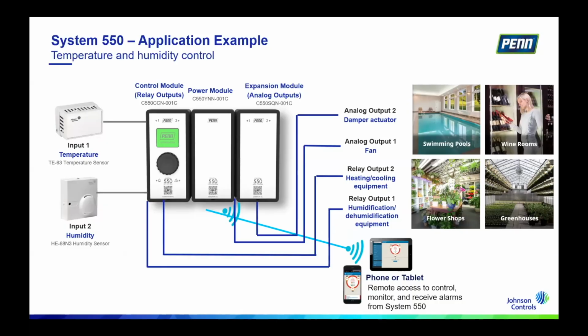Here's an application that Josh is showing here using a temperature and humidity input, where you're using the 4 outputs. You can see here the first output is to control the humidification and dehumidification equipment. The second output is a relay output controlling the heating and cooling equipment. And then you have 2 analog outputs. So that would be the last module on the right-hand side, which is an expansion module. And it's going to give a proportional output to control the fan and the damper actuator.